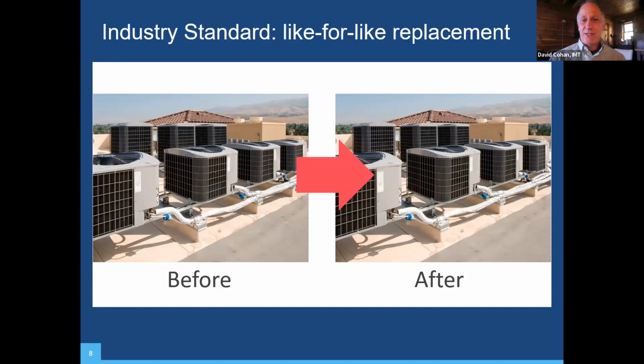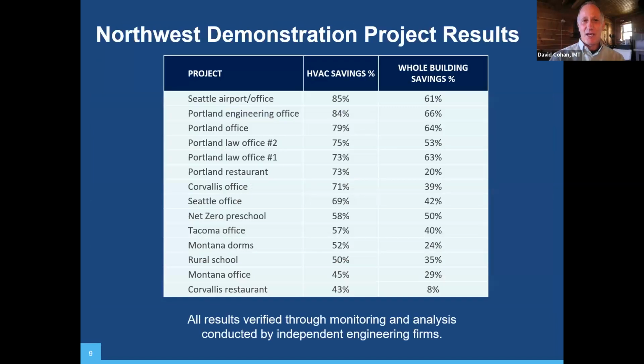If you have an HVAC problem right now and you call a contractor and say, I've got 4 ten-ton units on my roof, what should I do? Those pictures are identical, in case you're confused, because that's what you're going to get. They'll say, oh, you got 4 ten-ton units, we'll put 4 ten-ton units up just like that. All good. They are not going to ask whether there should have been 40 tons on the roof in the first place. They are not going to mess with your ventilation and make sure it's working right. They're just going to take those boxes off and put new boxes on. I'm not saying that's 100% of what happens, but it's 95% plus—like-for-like replacement. That's what they do.